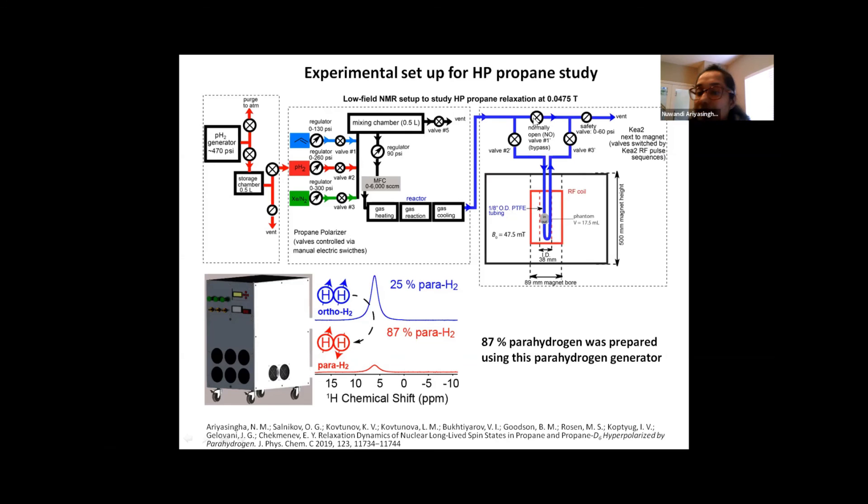The gas is sent using a different valve into a gas phantom which sits inside of an RF coil inside the magnet. And the gas flow is then directed to another valve into the atmosphere. And there is a bypass valve connecting the input and the output of the gas line into the phantom. The purpose of having this bypass valve is to ensure a continuous gas flow when the phantom is closed for the gas flow by closing valve numbers two and valve numbers three.